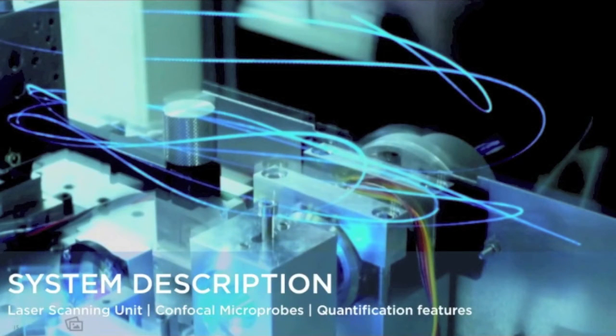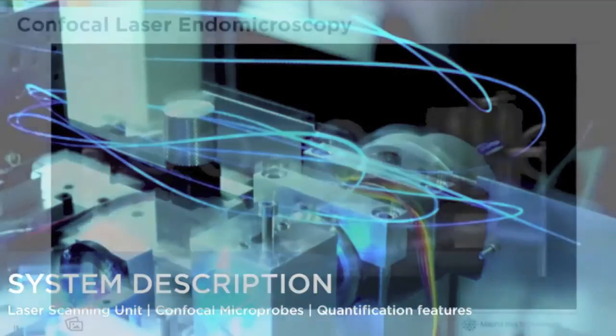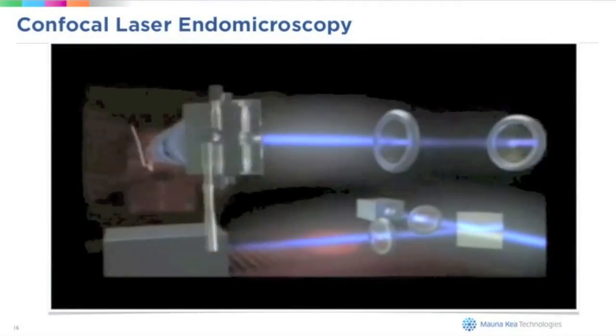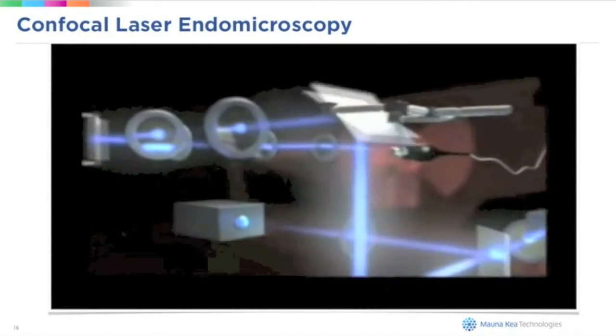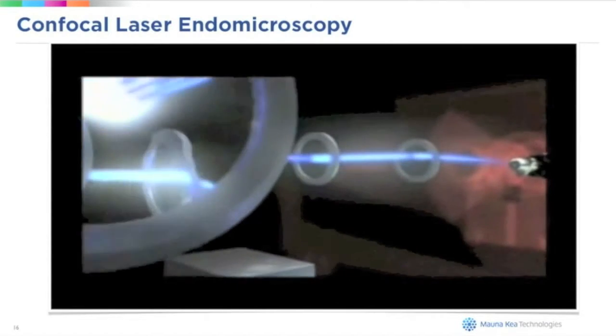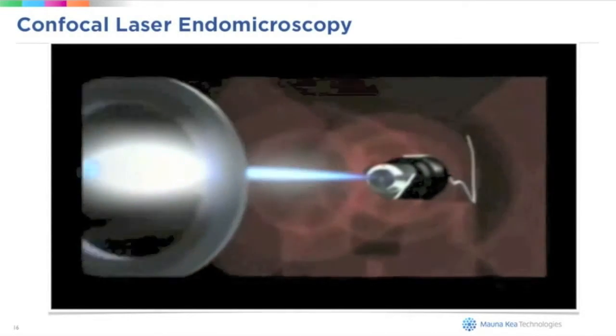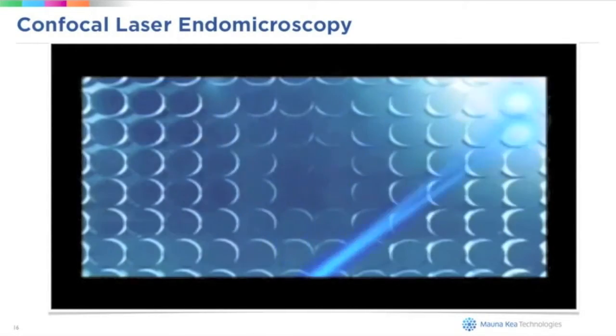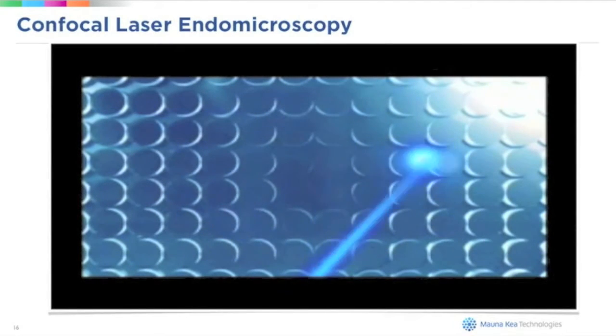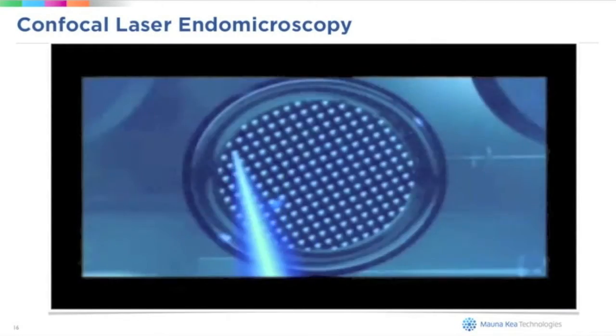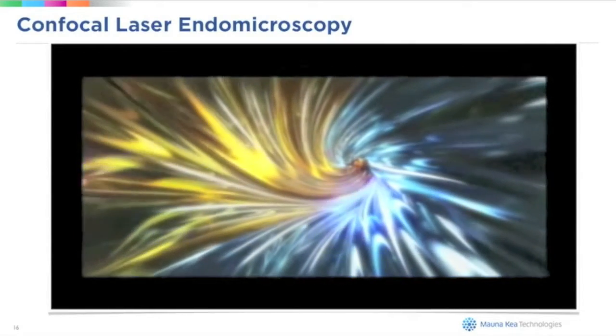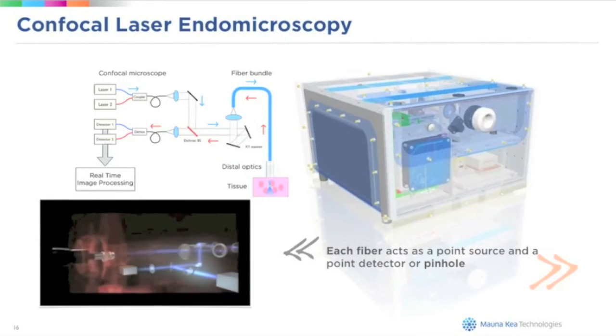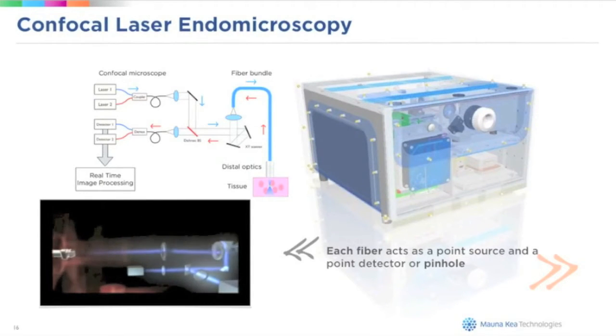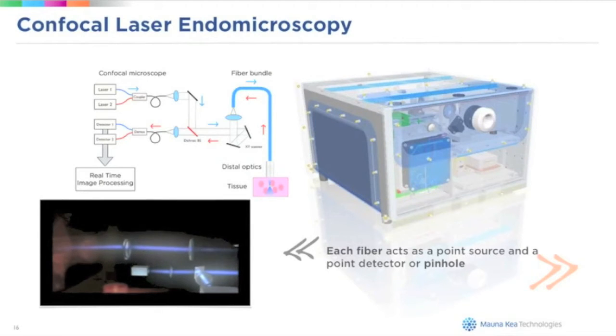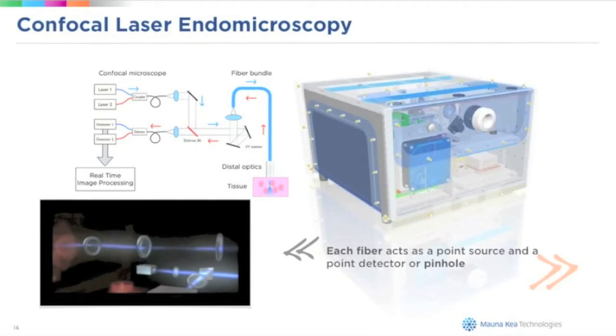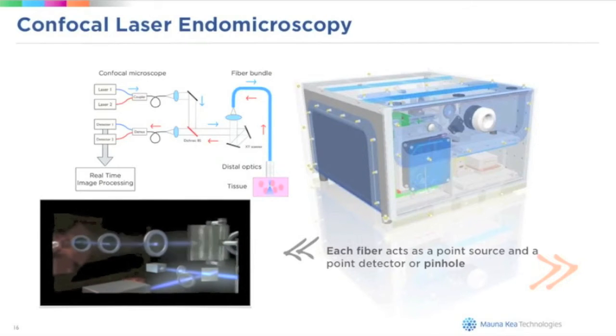I will now quickly describe to you the optics of the instrument. So the heart of the optical setup is made of two oscillating mirrors that you see moving here, and these mirrors are used to scan the incident laser light in the X and Y directions. We have a set of lenses that focus the light on the microprobe, and each microprobe is made of several thousands of optical fibers, from 10 to 30,000. The fluorescence emission of the sample is collected by the same fibers, and then it is sent to the detector.